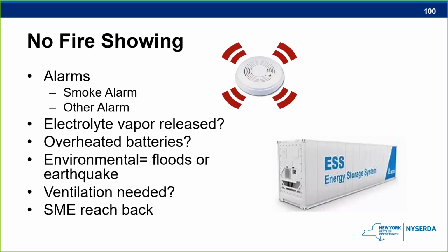For outdoor installations, there's really no reason for us to get in there. The batteries, if there is a heat source going on in there and we just haven't seen it yet, those batteries, after certain degrees, can no longer be used. So they're going to have to remove them anyway. They're not going to be put back in service. We also need to be concerned about environmental factors, like floods or earthquakes, if there is something that may have caused that to go away and maybe an internal short circuit had taken place.